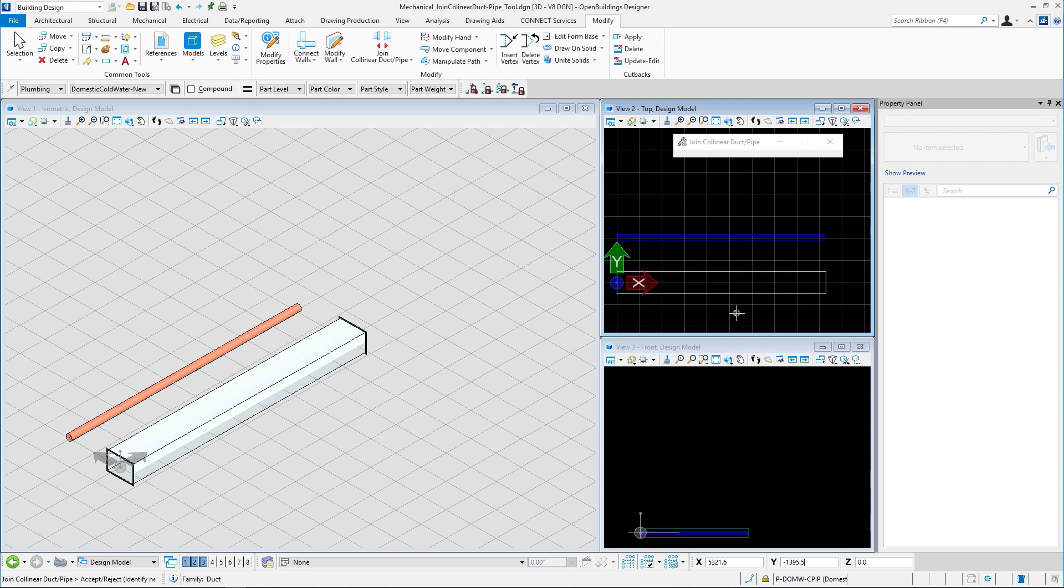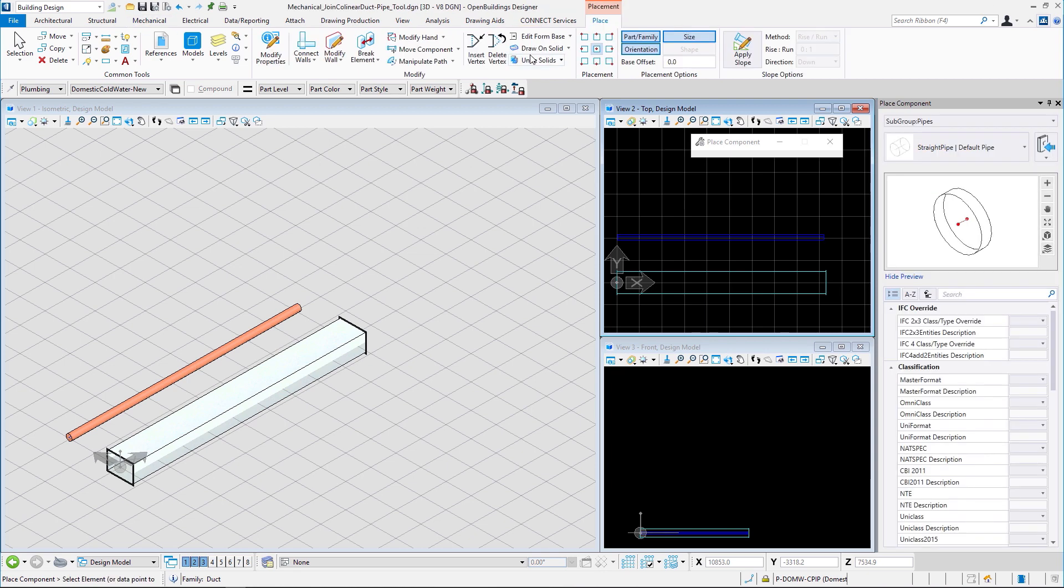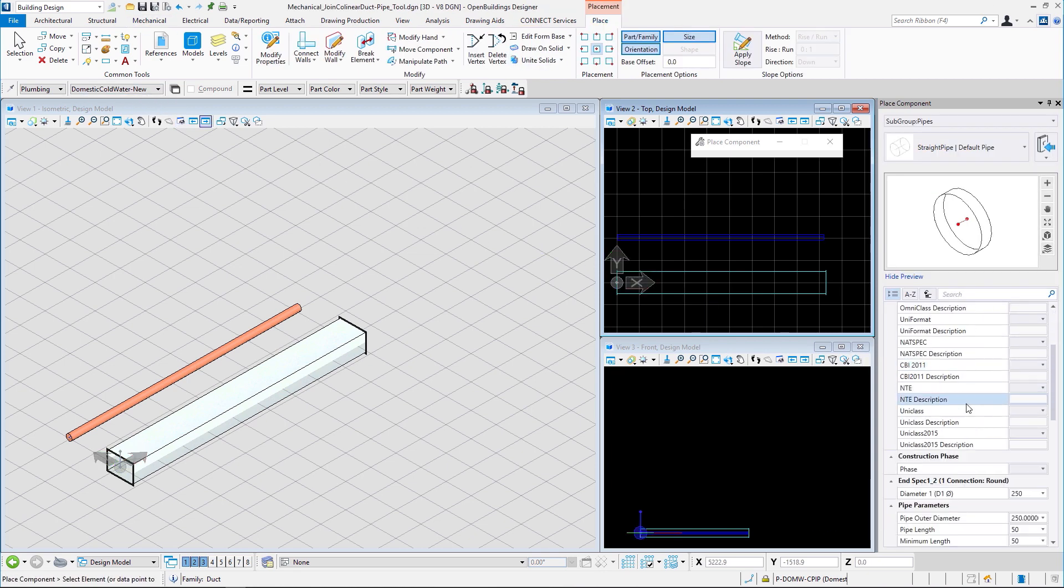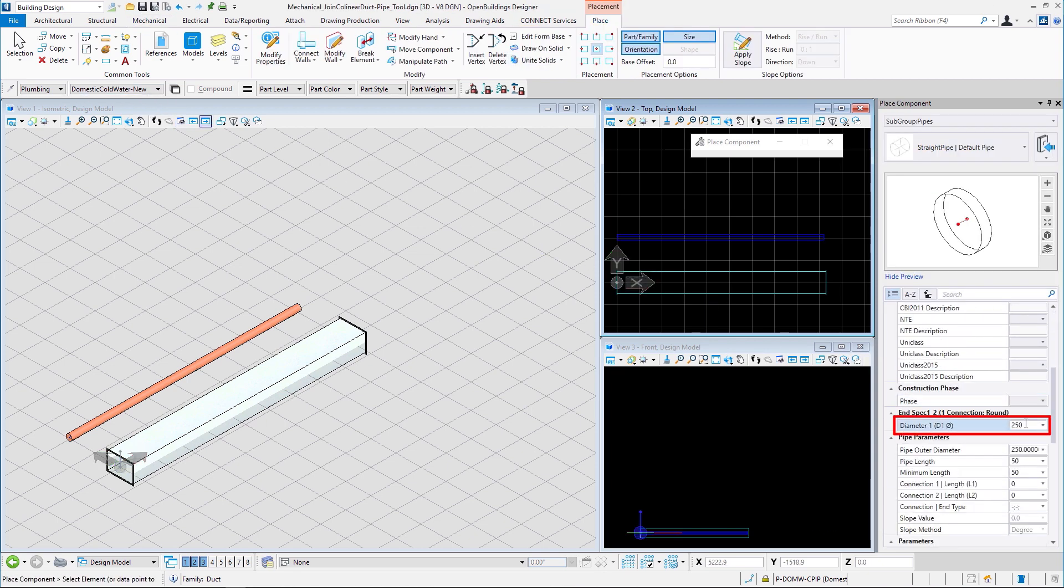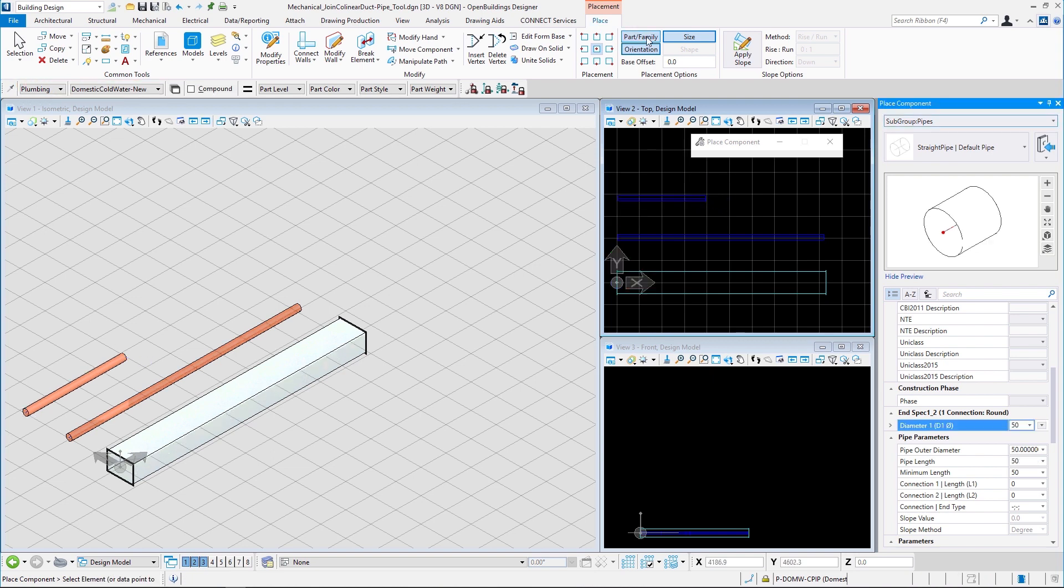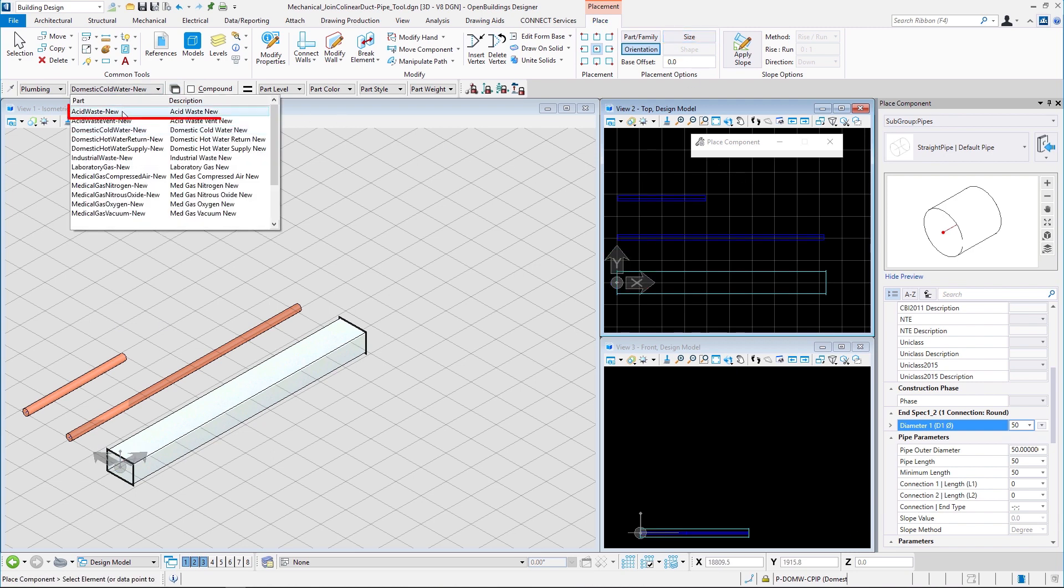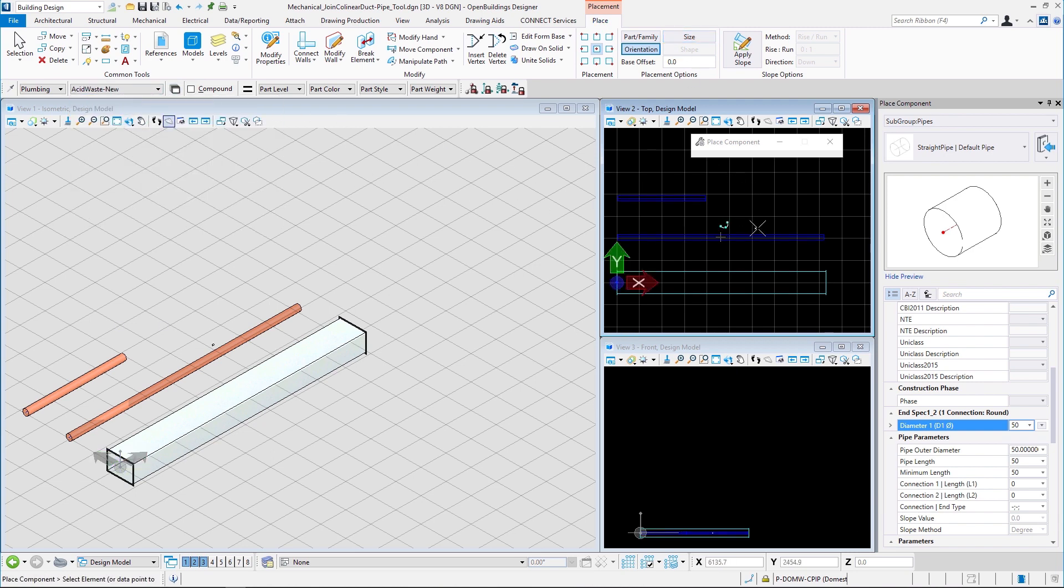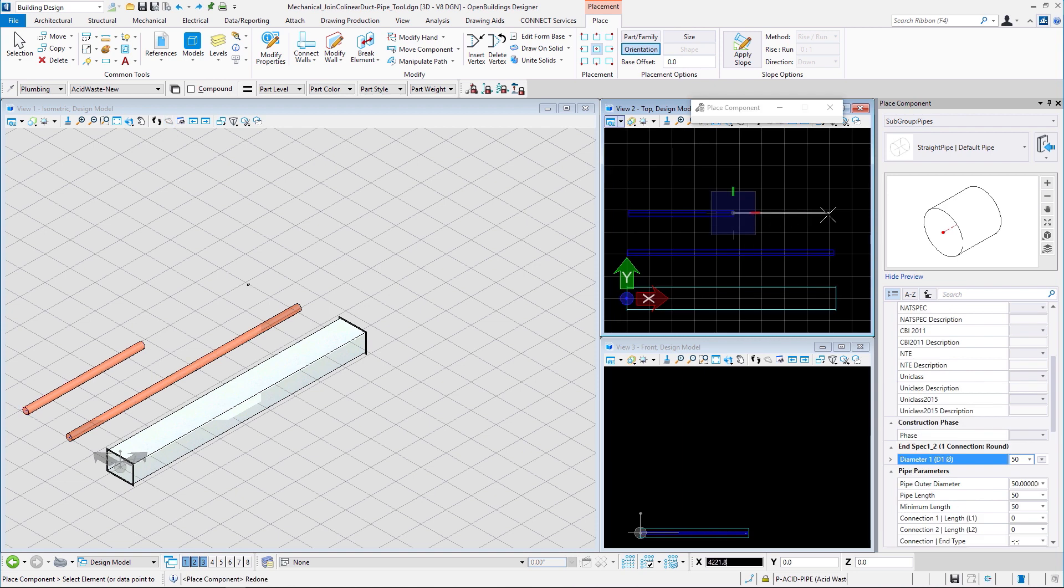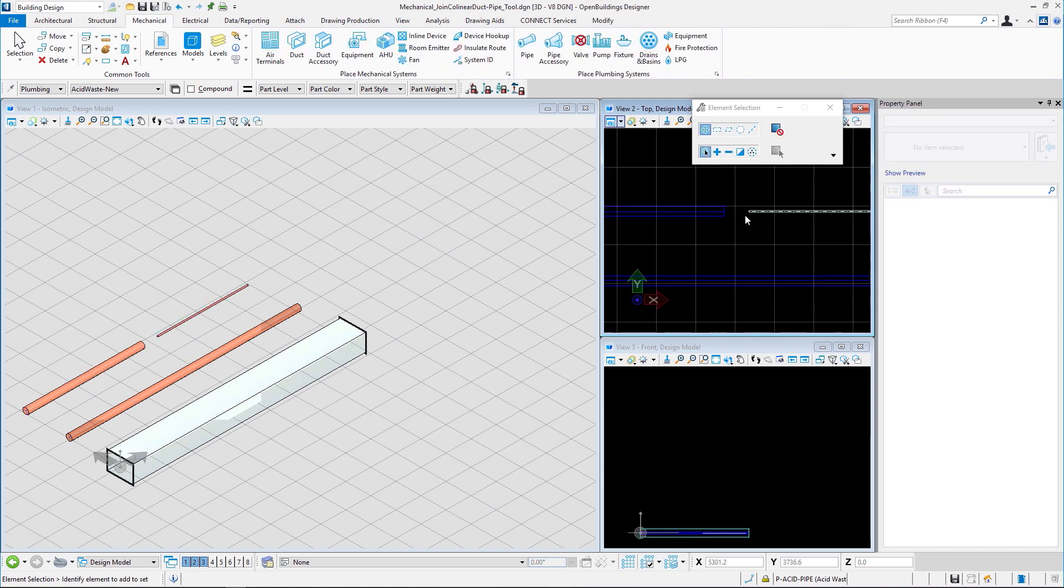Let us see an example of that. Let us go back to the mechanical tab, select the pipe tool and place a pipe with diameter 250 and family plumbing and part domestic cold water new. Now with the part family and the size toggle for the placement options turned off, let us choose part acid waste new and diameter 50 and place a pipe in such a way that these two pipes are collinear and touching each other.